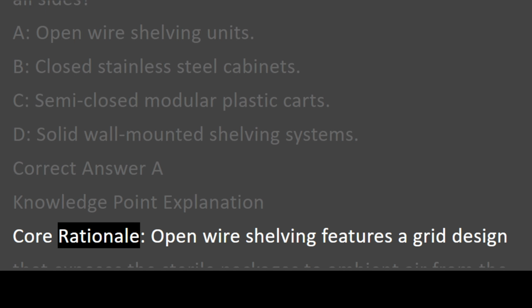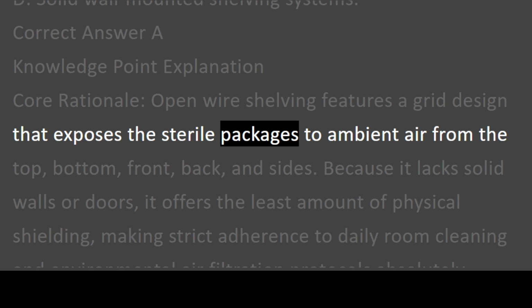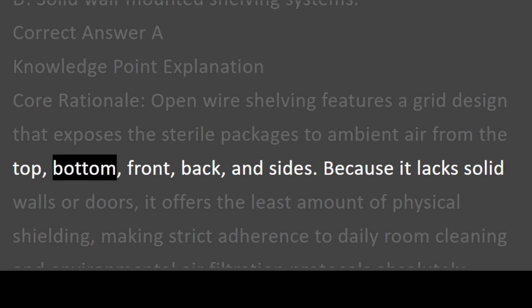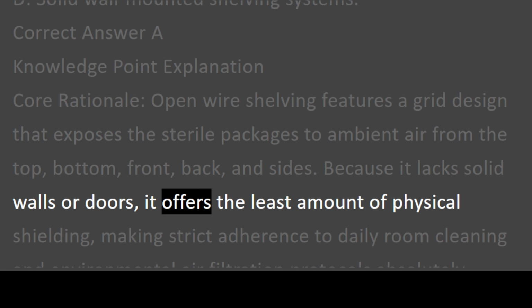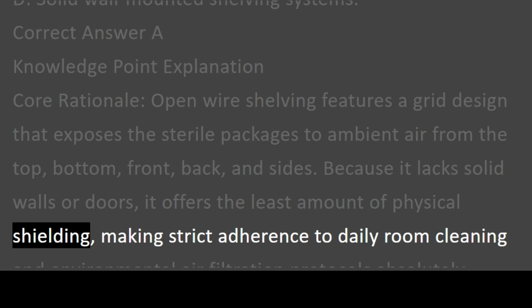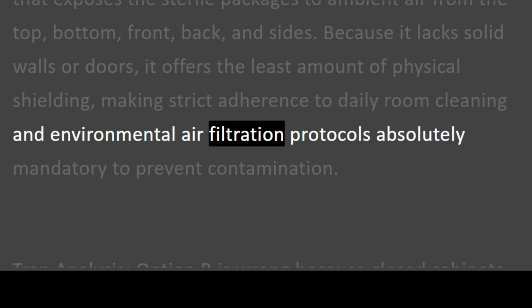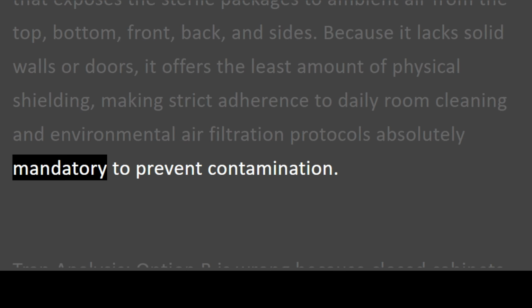Knowledge point explanation. Core rationale: open wire shelving features a grid design that exposes the sterile packages to ambient air from the top, bottom, front, back, and sides. Because it lacks solid walls or doors, it offers the least amount of physical shielding, making strict adherence to daily room cleaning and environmental air filtration protocols absolutely mandatory to prevent contamination.